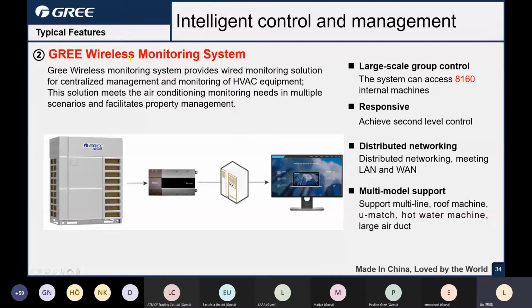So for the first one, the wireless monitoring system. Here, this is our monitoring software. Through this software, you can monitor the running of GMV6 on your computer. And this monitoring system can realize very large scale group control. The system can be up to 8,160 indoor units. That's the maximum for just one set of software. So you know the expansibility of this monitoring system is very good. I think currently maybe no project can exceed the limit.